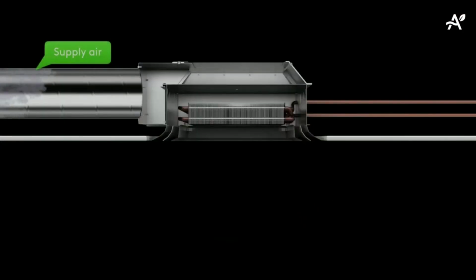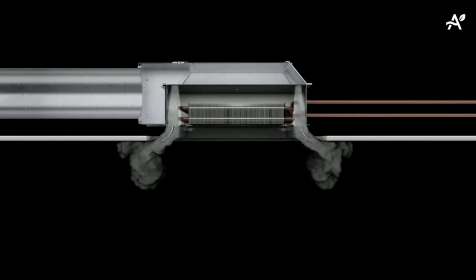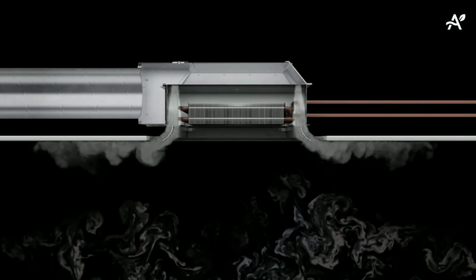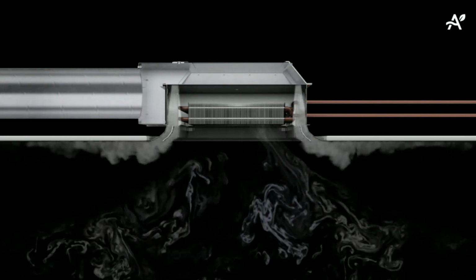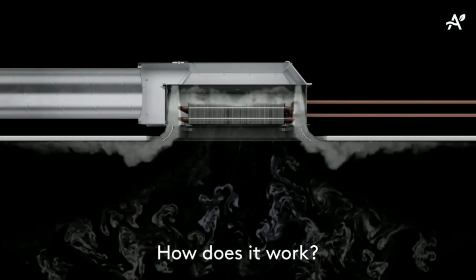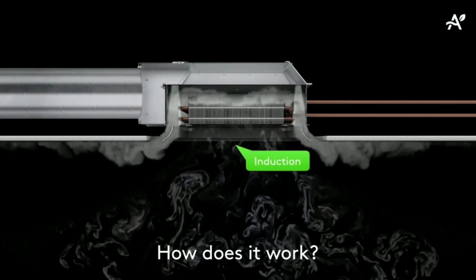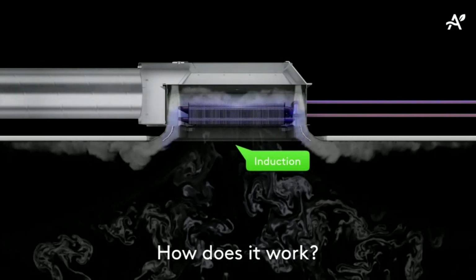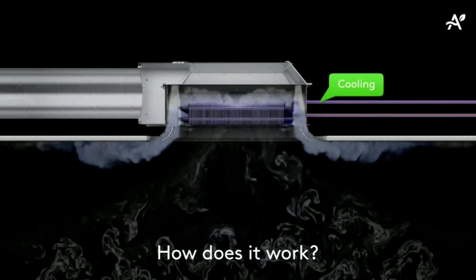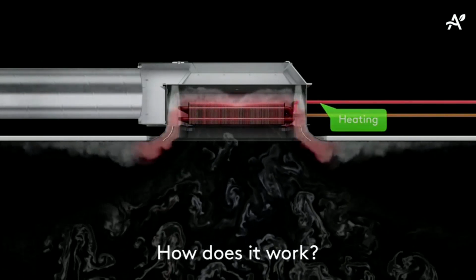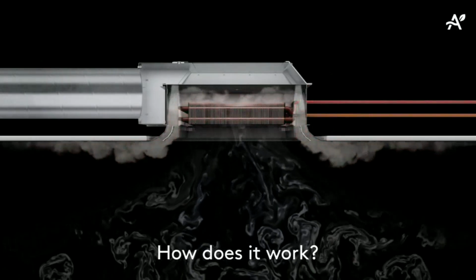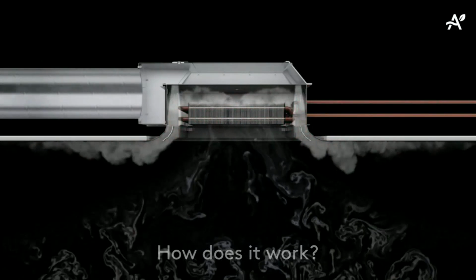So the chiller and the heat pump can only produce either cheap cold water or warm water. And when you produce warm water, and we still need cooling here because it's a conference room full of people, we can use the air to cool down this room while we heat up the rest of the rooms. So it's very important to design the system in a correct way to give everyone the climate they want on this floor. Exactly. Even if we were working with a 2-pipe system, yes. Good.